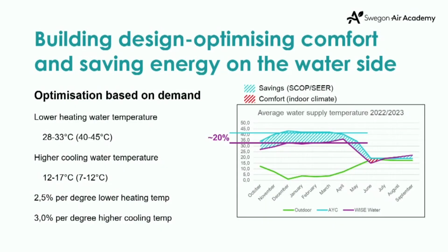So, but let's go back a little bit and look at these optimizing functionalities and how to optimize both the comfort and energy savings on the water side. Yeah. So, the importance here, and this is where we save the energy, for every degree of higher water temperature that we need to produce in cooling mode, we save 3% of energy. And for every degree of lower water temperature that we need to produce in heating mode, we save 2.5%. So in this particular building, by working with demand-controlled water temperatures instead of outdoor compensated temperatures, we save approximately 20% energy during the winter time.